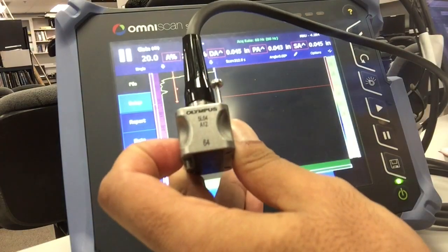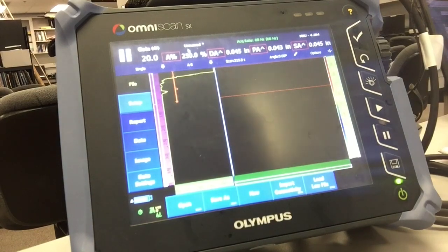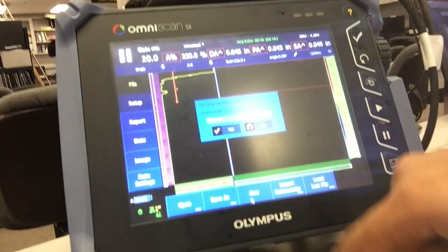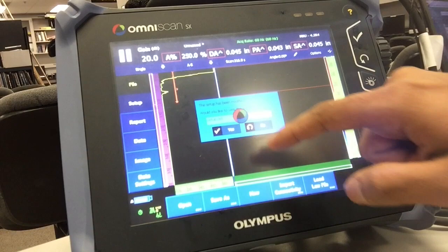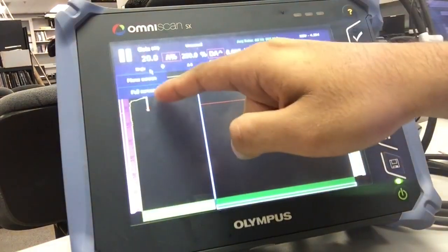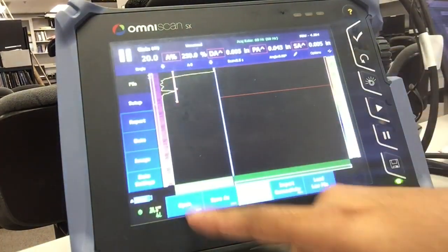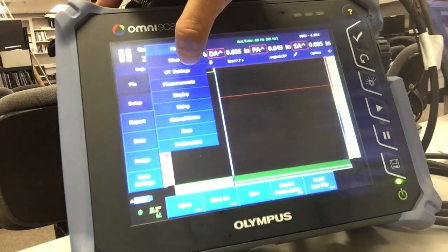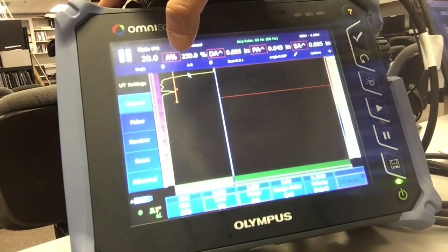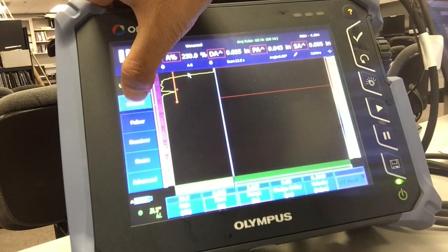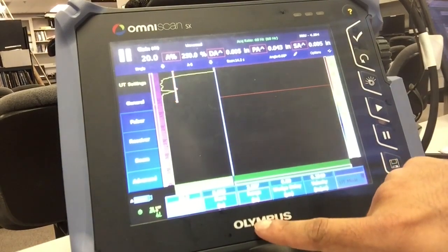Okay, so let's start with the dead element check for this probe, which is 5L64. The first thing I want to do is create a new setup, so I start afresh. Then I go to menu screen and click on UT settings. I want to change my range, so I go to general and click on range.